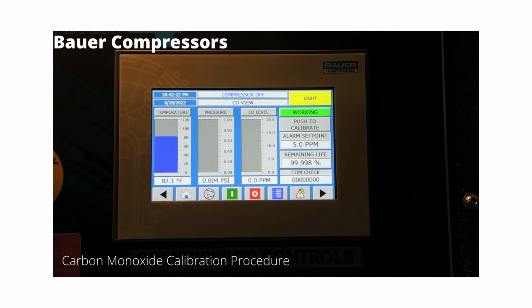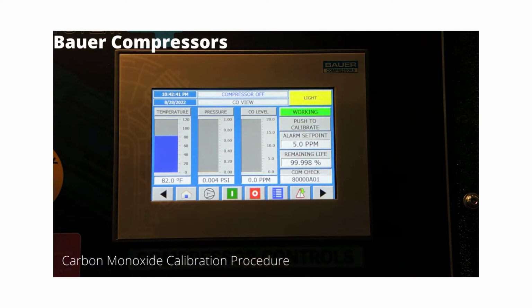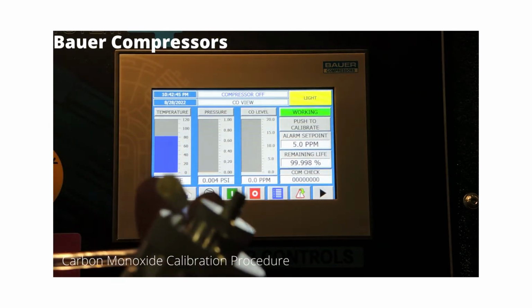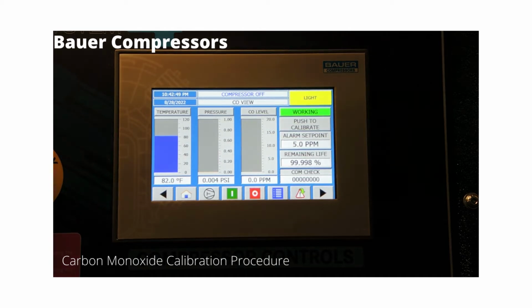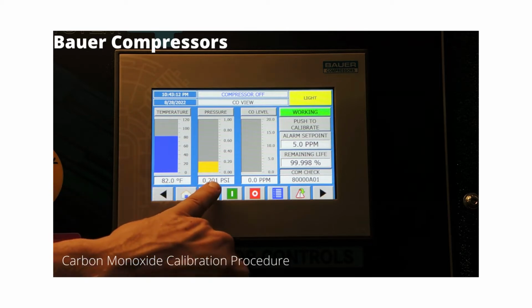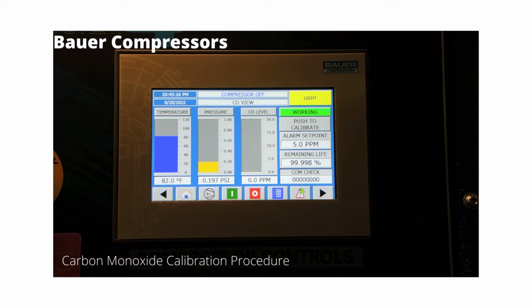The first gas that we're going to connect is our 0 air, and that's going to be cylinder 20. So we're going to connect the regulator, and then at the CO monitor, once you find it, you're going to quarter turn the blue hose off, and then you'll be connecting the quarter turn connection to the end of the sensor. So I'm going to find that, and then we're going to make that connection. One of the things I like to do is make that connection and make sure that it recognizes pressure. So I'm now flowing 0 air to it.